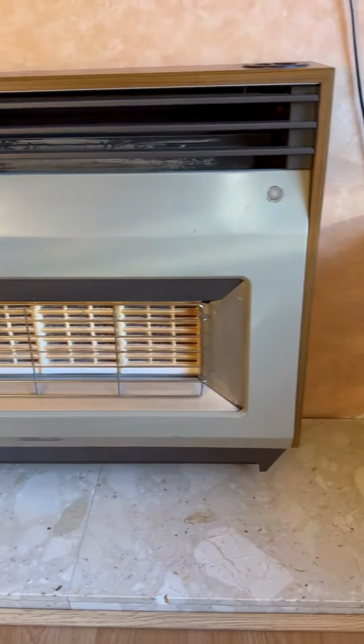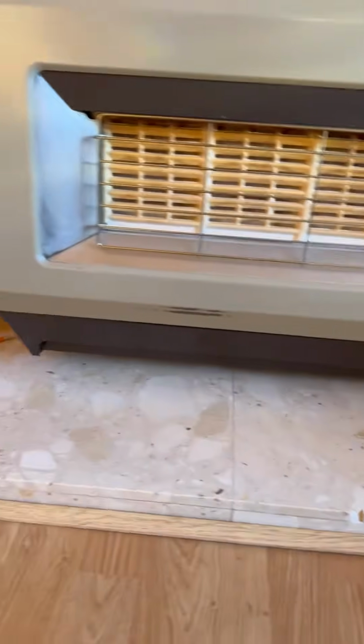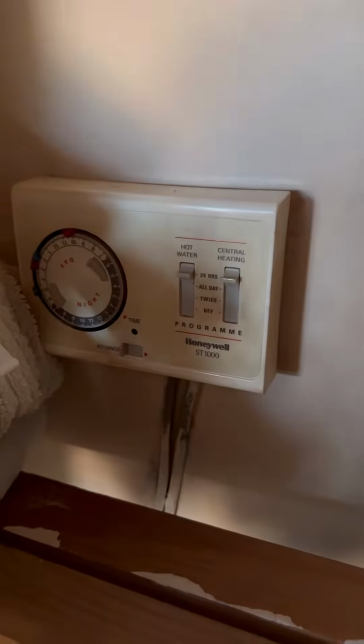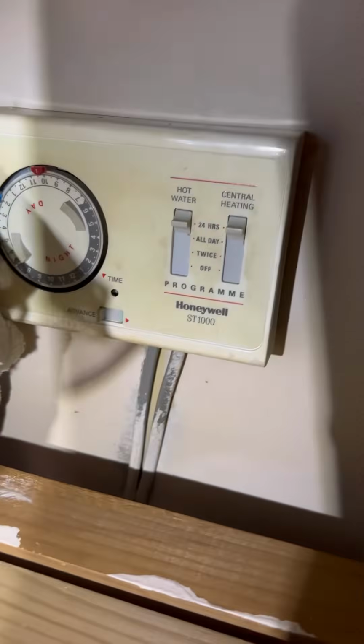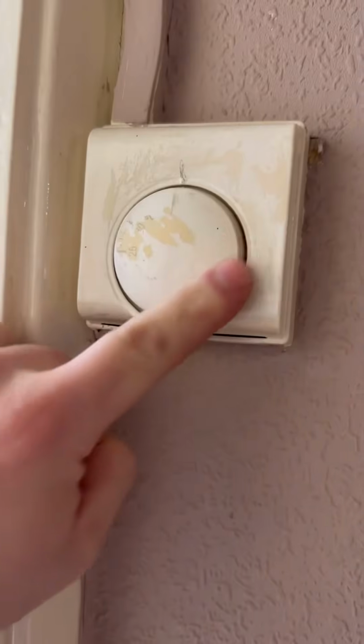Turned up to this old back boiler, no heating, no hot water was the fault. Have a quick look at the back boiler. Go to the programmer, it's calling for heating and hot water. Room stat's calling. Pilot light's just sat there, boiler's not doing anything.